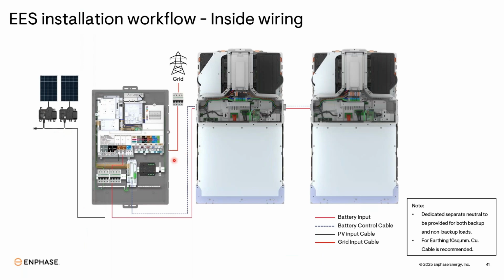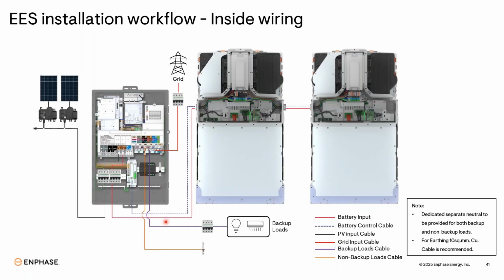Your grid cable input will come here. From here your backup loads output, your non-backup loads output. This is your rapid shutdown switch, the system shutdown switch you can say. So make sure you use separate dedicated line and neutral for both backup and non-backup. Separate neutral will be there.